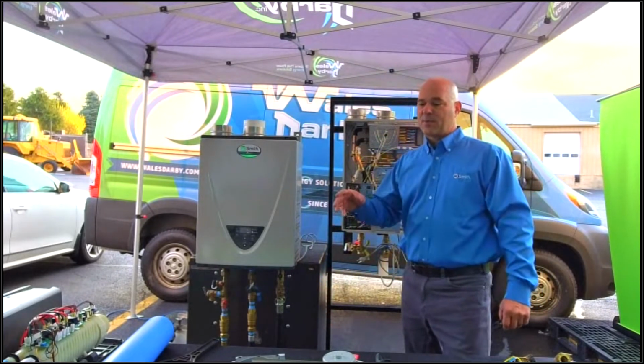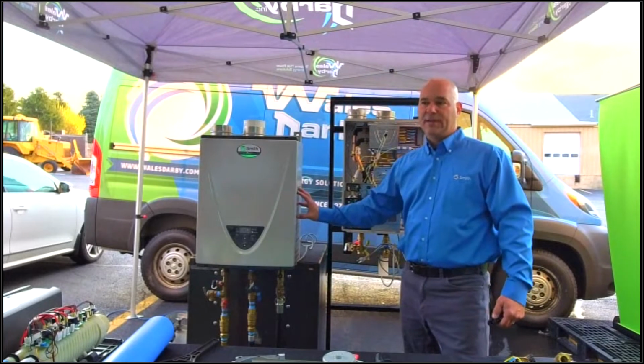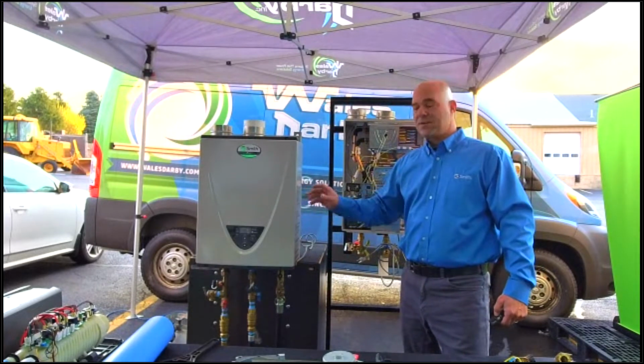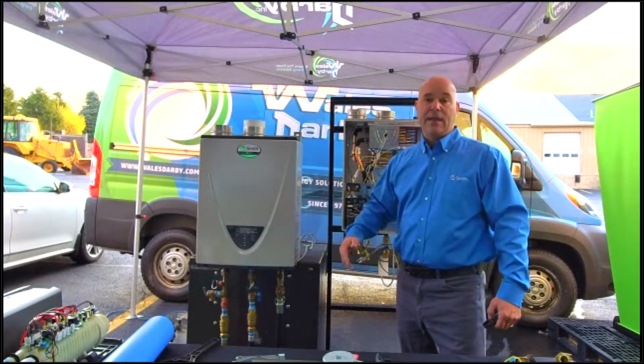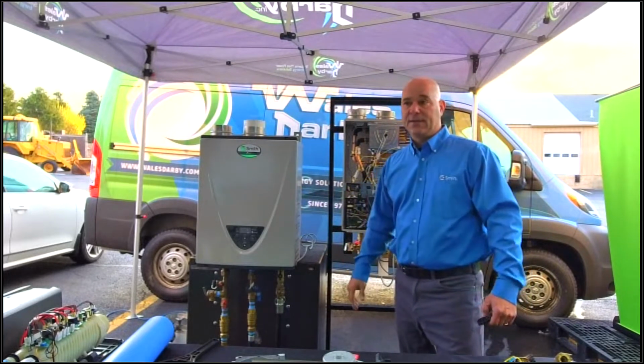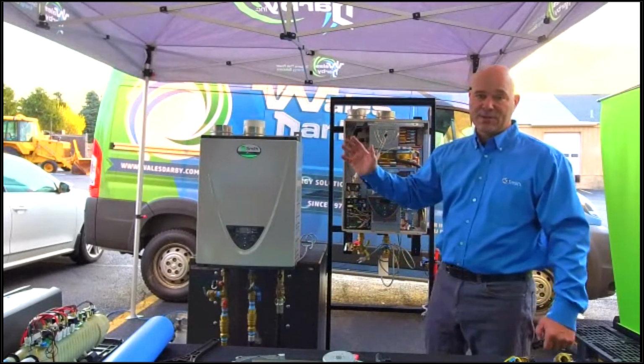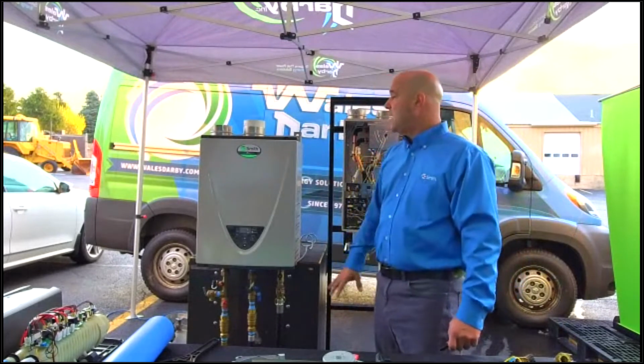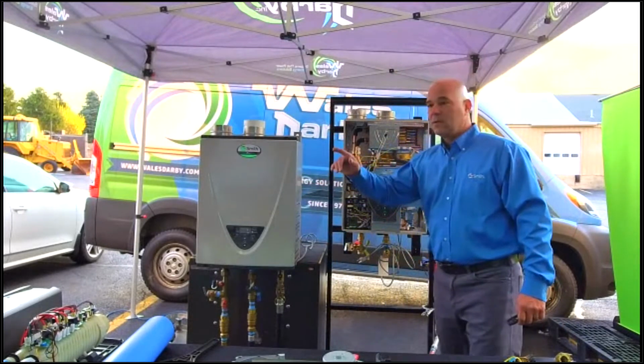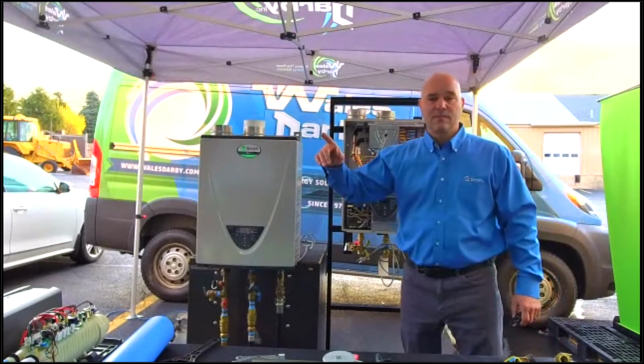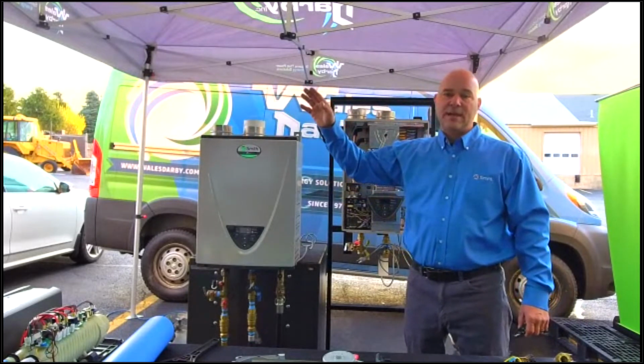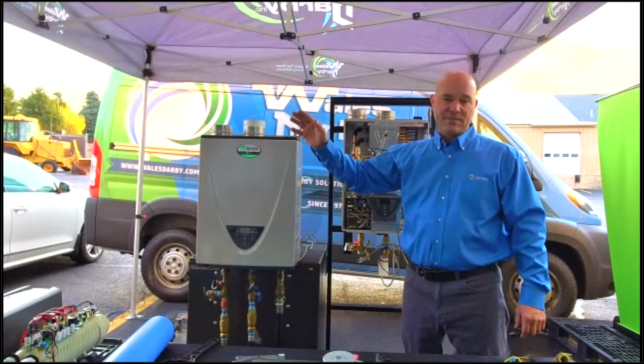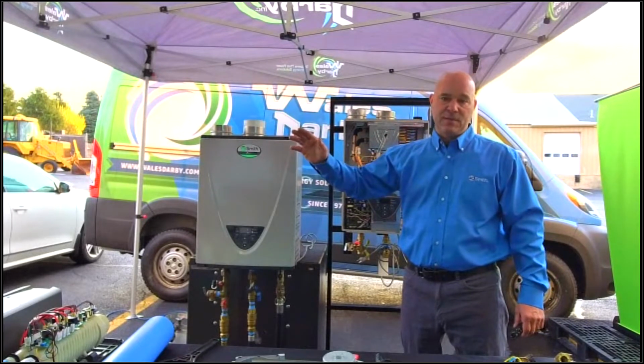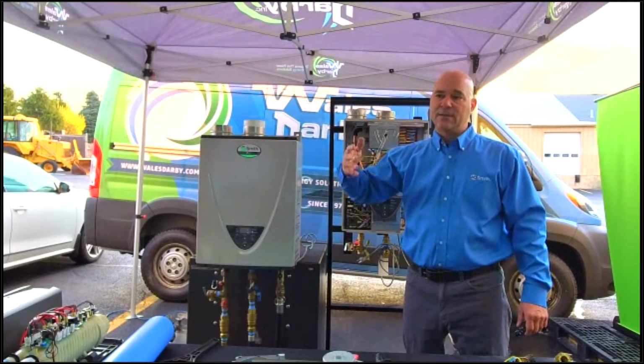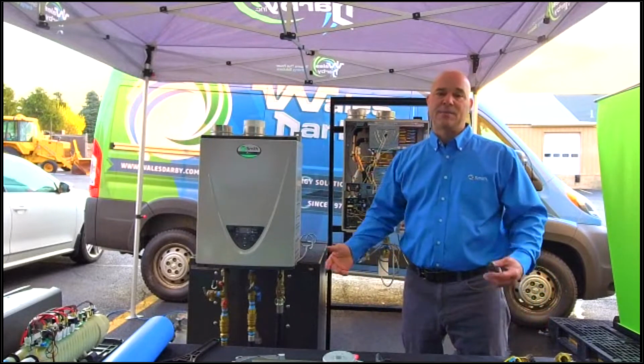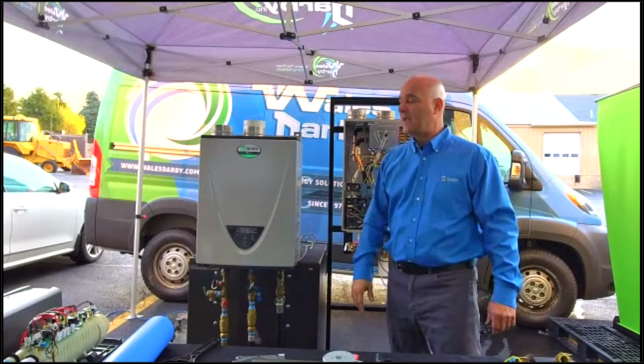And the main reason for that product preserver is we want to keep the heat exchanger clean. And the cleaner we keep the heat exchanger, the more performance we get out of it, and the longer life we will get out of the heater. And again, brand X, Y, or Z. Okay, gas side, 140,000 BTU, 160,000 BTU, 180,000 BTU, 199,000 BTU. They all modulate down to either 15 or 13,000 at the bottom, depending on if it's natural gas or propane.